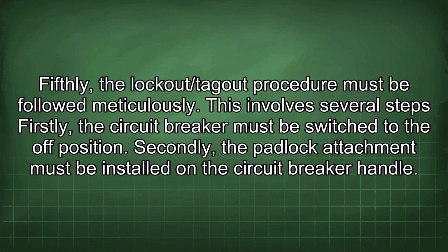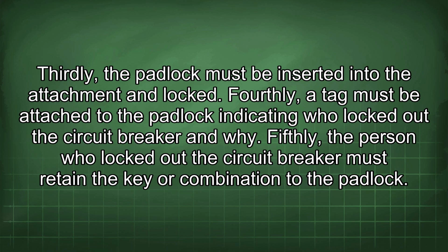Fifthly, the lockout/tagout procedure must be followed meticulously. This involves several steps. Firstly, the circuit breaker must be switched to the off position. Secondly, the padlock attachment must be installed on the circuit breaker handle. Thirdly, the padlock must be inserted into the attachment and locked. Fourthly, a tag must be attached to the padlock indicating who locked out the circuit breaker and why. Fifthly, the person who locked out the circuit breaker must retain the key or combination to the padlock.